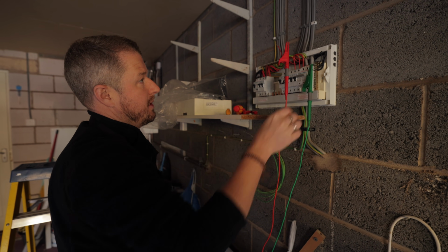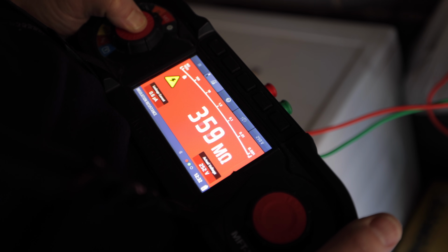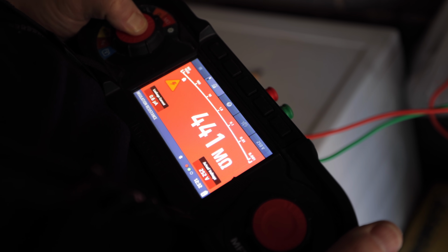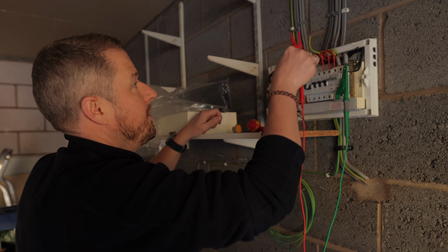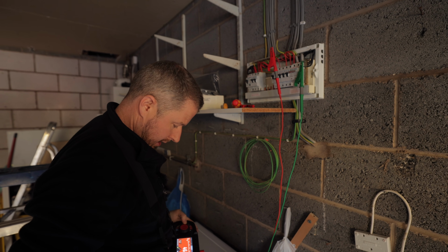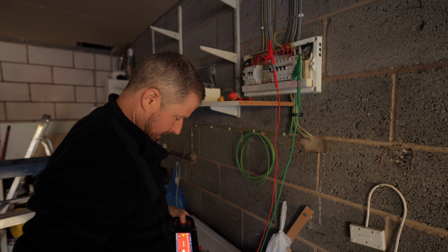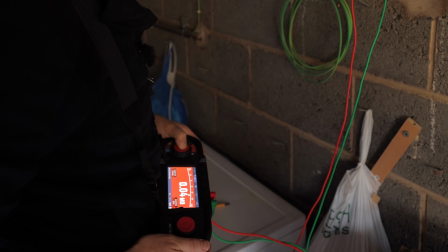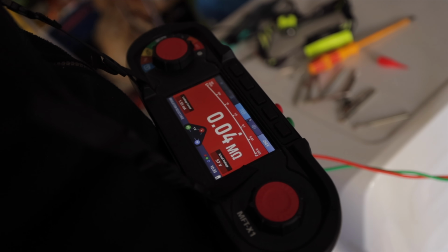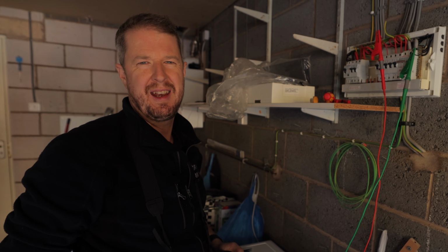But let's try between the neutral and the earth. Okay, so we've also got high resistance there. So according to this, everything seems like it should be fine. Test between live and neutral, and we should have basically a dead short, which is what we've got. We've got 0.04 megaohms. That all seems fine. It just doesn't make any sense.